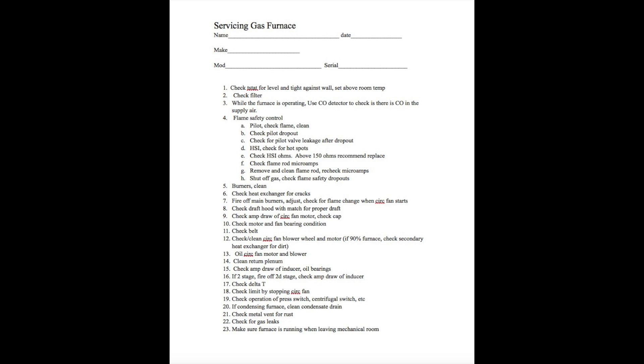If the furnace has an inducer, check the amp draw of the inducer when it's running. It should be at or below its rated load. Check the bearings of it while you're there. Does it turn smoothly? Is there excessive clearance in the bearings?